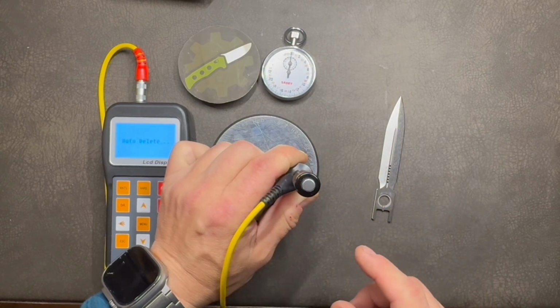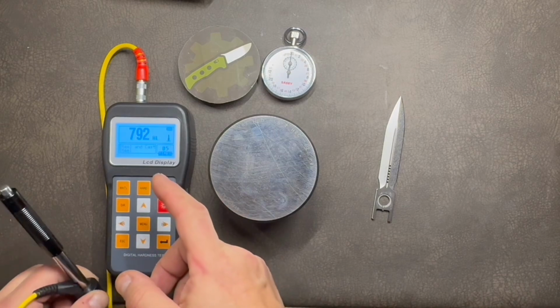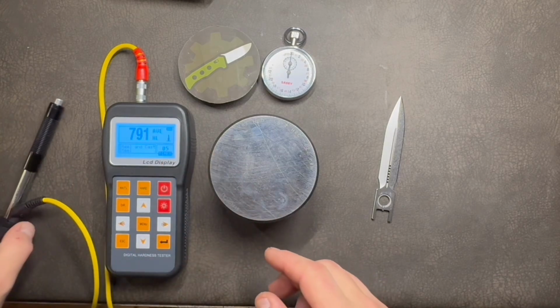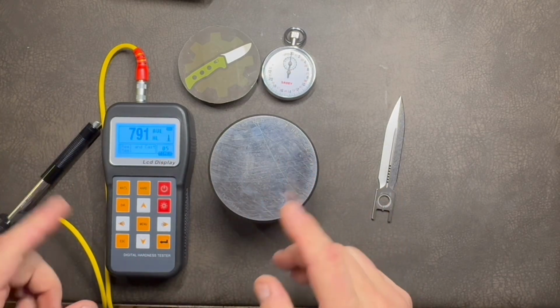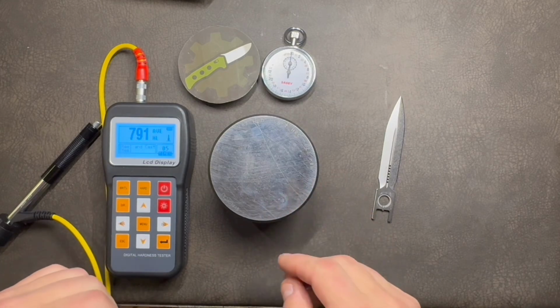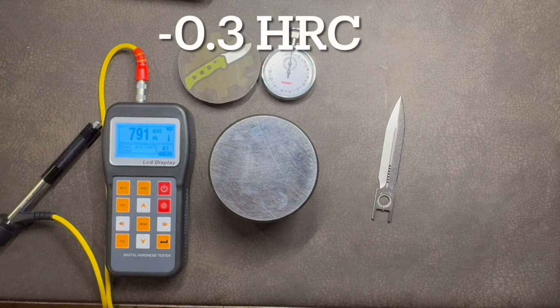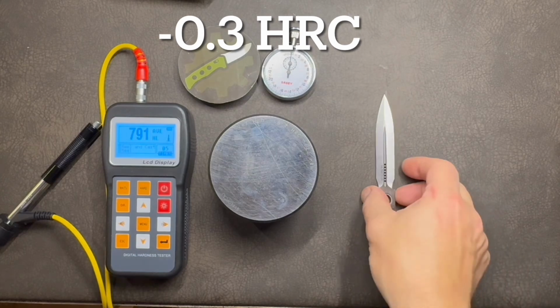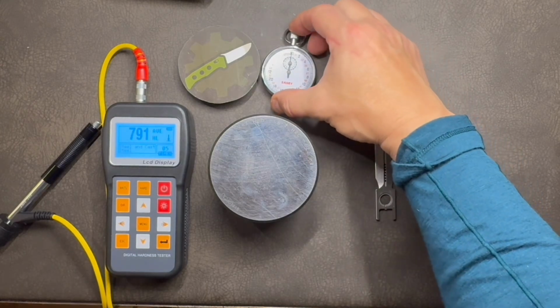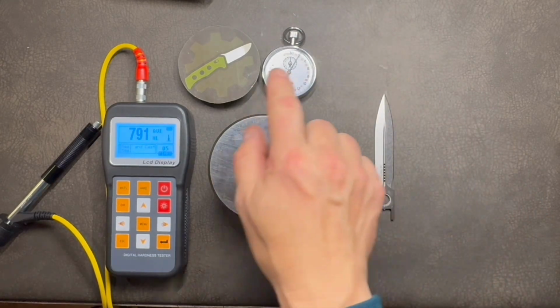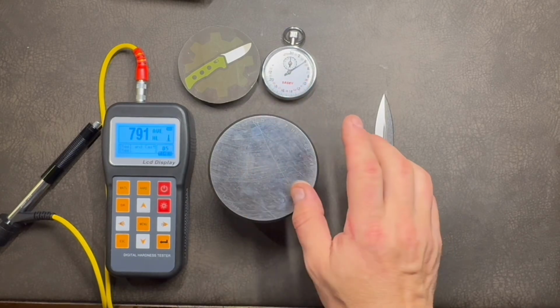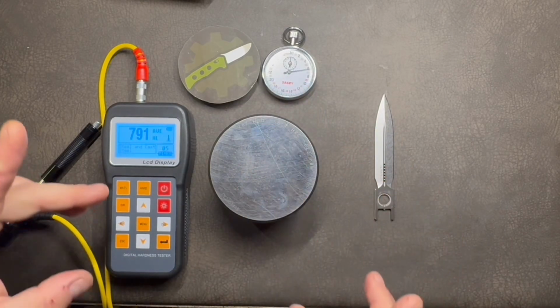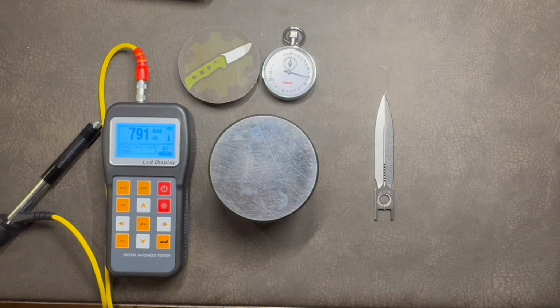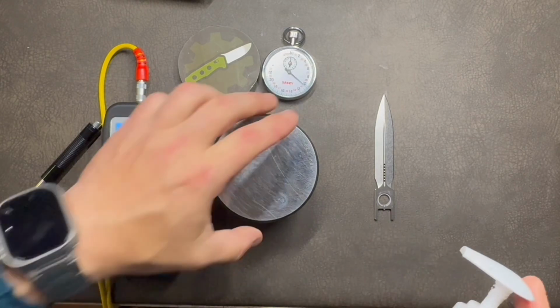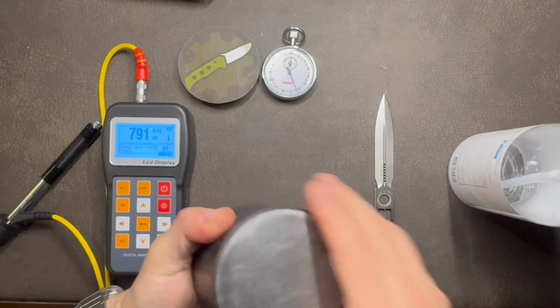This beep is telling me that it's calculating an average, and we got 791 points, which is 4 points above calibration. We're going to be subtracting 0.3 points on the Rockwell scale. I start the stopwatch so that the sweep of the handle illustrates to you that I am not editing this segment. It's going to be one continuous and uninterrupted experiment.